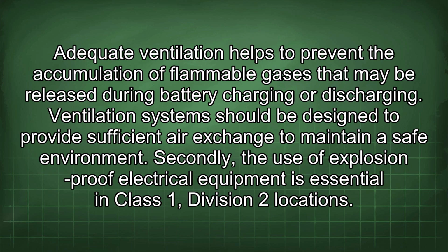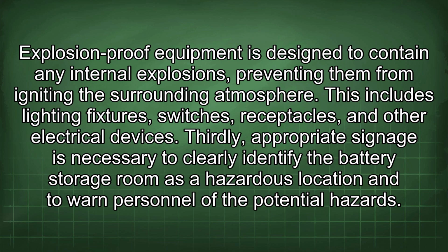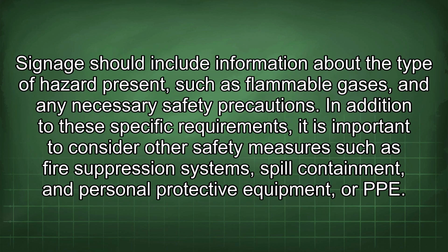Secondly, the use of explosion-proof electrical equipment is essential in Class 1, Division 2 locations. Explosion-proof equipment is designed to contain any internal explosions, preventing them from igniting the surrounding atmosphere. This includes lighting fixtures, switches, receptacles, and other electrical devices. Thirdly, appropriate signage is necessary to clearly identify the battery storage room as a hazardous location and to warn personnel of the potential hazards.